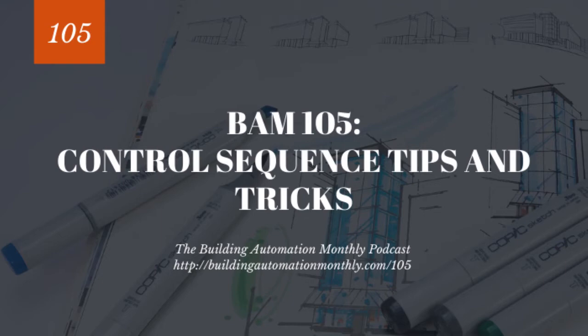You're going to then move into tip number 2, which is rearranging if necessary, but without changing. And this is actually quite a difficult skill to master, because anyone could go and rearrange a sequence and say, oh, look, there's that start sequence at the end of the sequence of operations where it actually says how to start the fan. I'm going to move that to the top because that's where my start condition is, and I'm going to move it to the top of the sequence when I rewrite it. That way, whoever's programming it, or if I'm programming it, that's how we're going to do it. But you've got to be careful when you do that, because when you get to complex sequences like chiller plants or multi-fan air handlers with building static pressure tied to the air handler's control, or maybe some resets based on VAV units, you can start to have complexity.